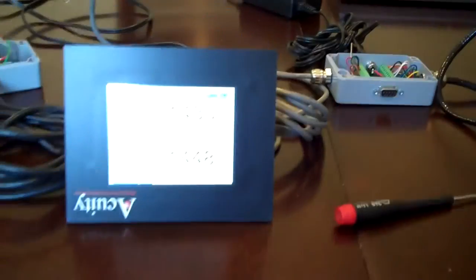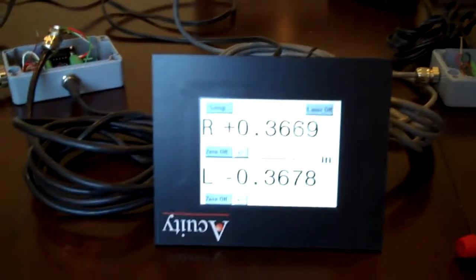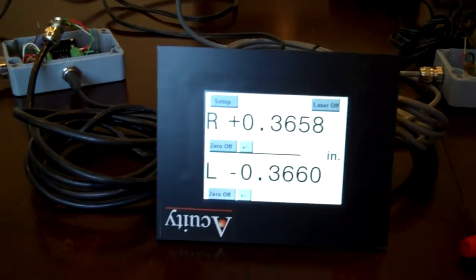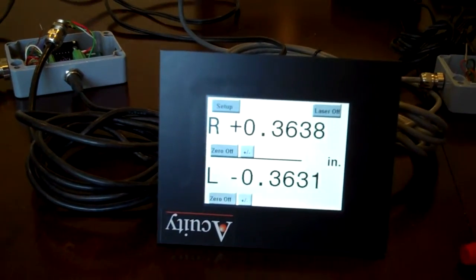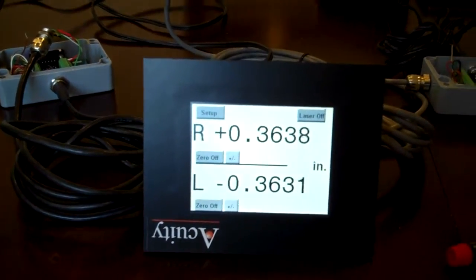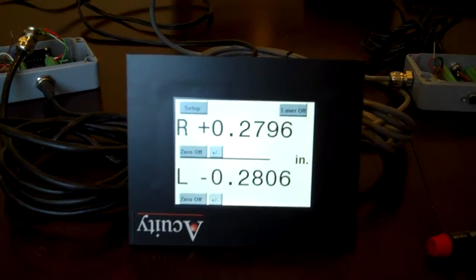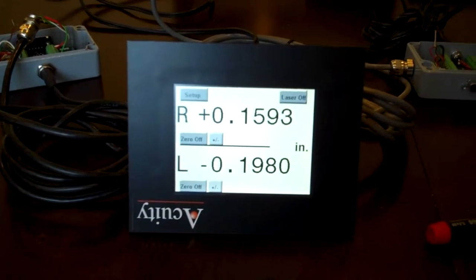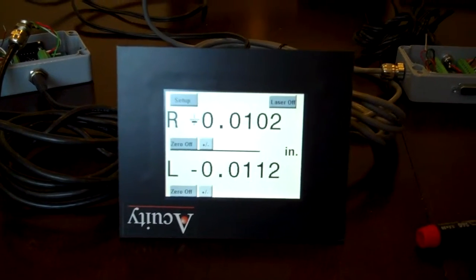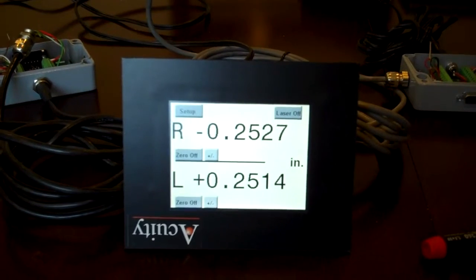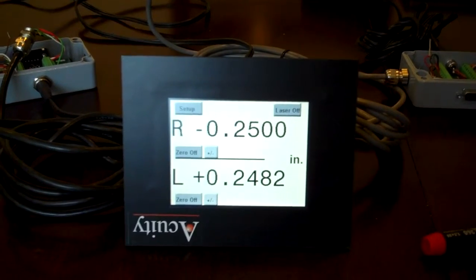Now as you move an object through the measurement range, they should read the same number but with the opposite sign. So as you move an object left to right, one is reading the inverse of the other. And as you can see, that is the case here.